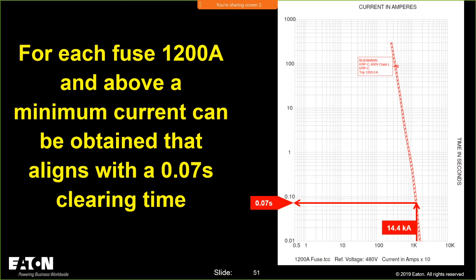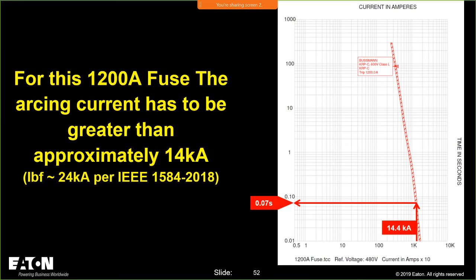Now, I already showed you this screen, and I can tell you that for that 1200 amp fuse, the arcing current has to be greater than approximately 14,000 amps. If I reverse engineer the solution and use IEEE 1584, I actually used SKM, the bolted fault current has to be greater than 24,000 amps. Now, the chances of you applying a 1200 amp fuse when you have fault currents less than 24,000 amps are probably slim to none. You're probably going to end up using a circuit breaker in that application. But if you have a fusible solution for whatever reason and your bolted fault current is less than 24,000 amps, you're going to need an arc reduction technology.